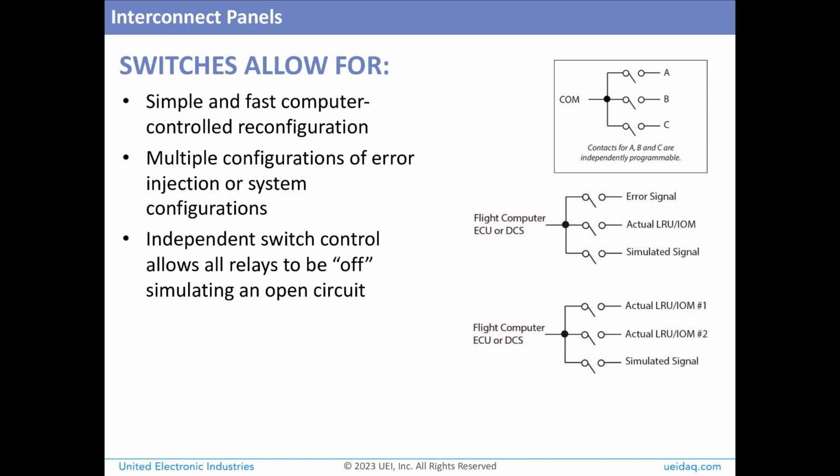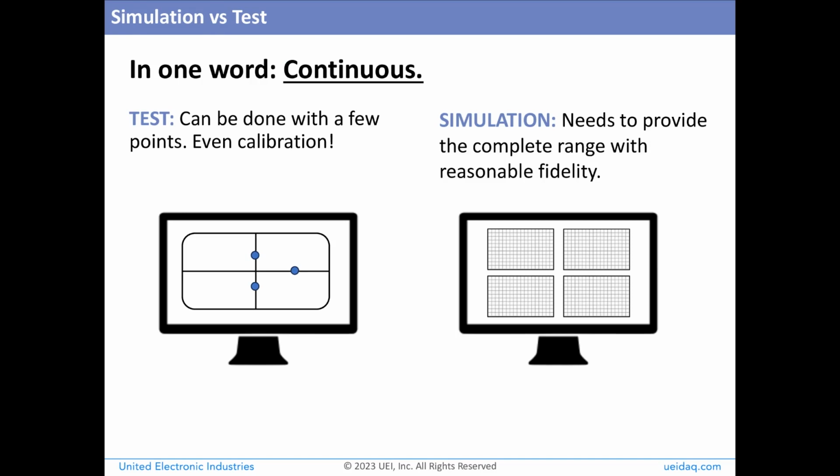Typically, all these systems go through interconnect panels, and we have methods to handle interconnects using a computer-controlled interconnect board. The ability to switch in the real signal, the simulated signal, a fault, or even an open is invaluable for range and error checking for those faults. Or switch in multiple faults. Take control of your HIL, SIL, or your hybrid test bench. Sure, trust but verify, but don't just verify one point, which brings us to this next point.